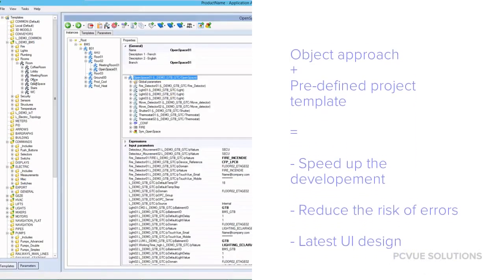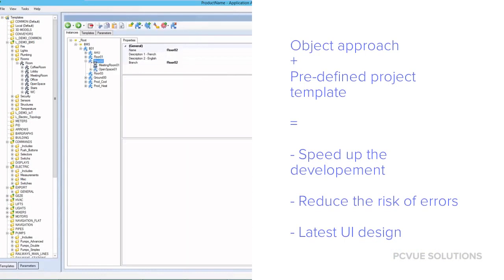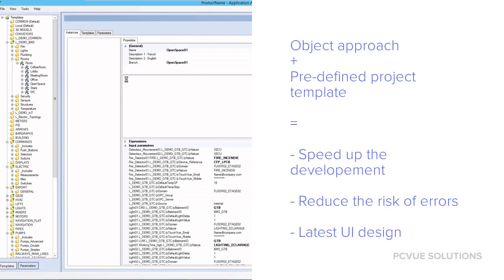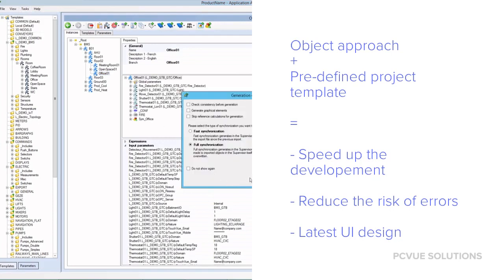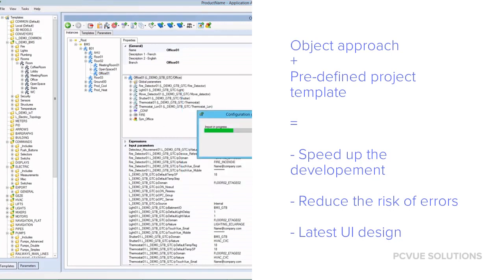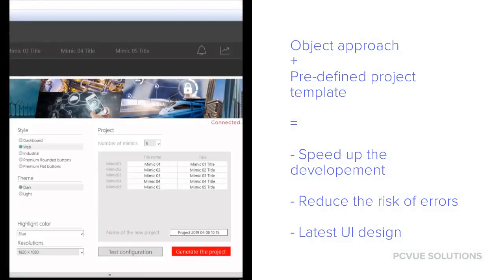An object-oriented approach avoids the creation of duplicate animations for each mimic and greatly accelerates the development process. This approach also speeds up implementation of changes during the test phases or later application changes. It dramatically reduces the risk of errors by ensuring the modification of an object will be reflected everywhere the instances of it are used.